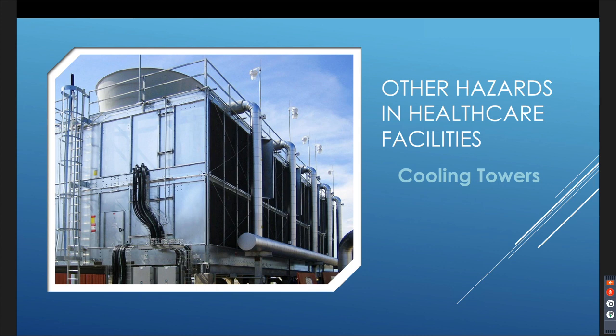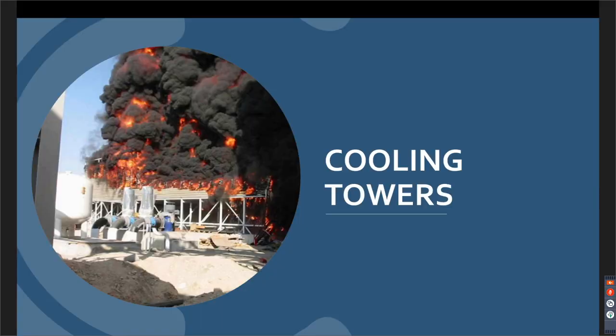Cooling towers may be prevalent on your facility and may be required. Are cooling towers hazardous? Usually not while they're operational. However, when they are allowed to sit or they're taken out of service, something special happens to the wood that creates a very highly combustible situation in these things, and they burn really, really readily.